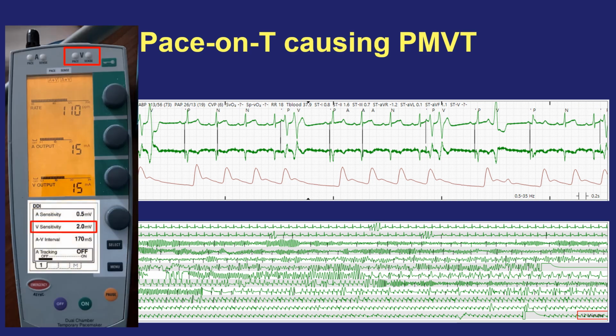Here we have this ventricular sensitivity number. Again, just to remind you that if you were to see this pacing on T wave, we would do the opposite of what we did before when there was oversensing. Here we're having undersensing, and we want the ventricular lead to be more sensitive. So in this case, we would make this number smaller until we reliably saw the sensing light flash with each native QRS complex, reflecting accurate sensing of intrinsic cardiac activity.